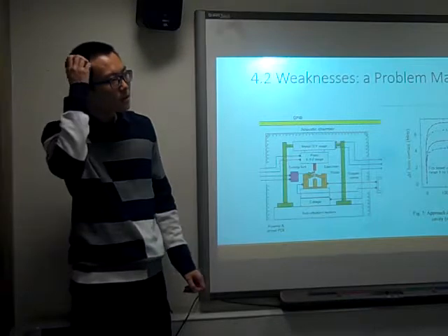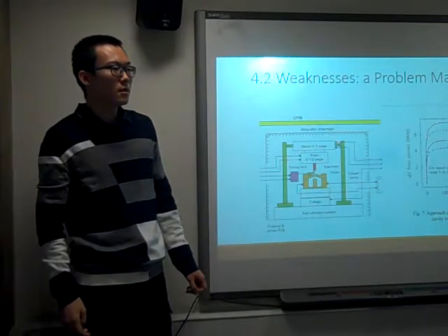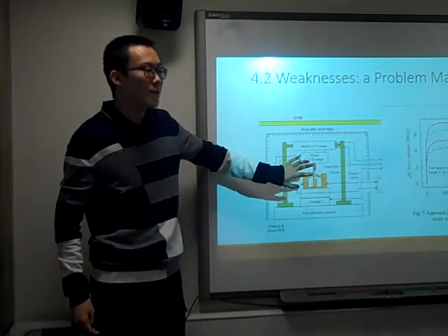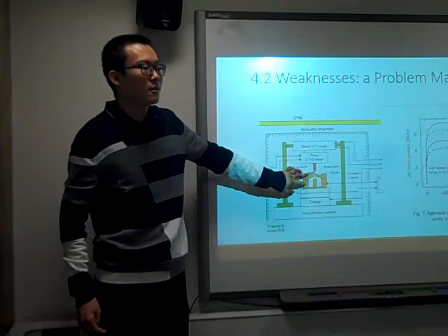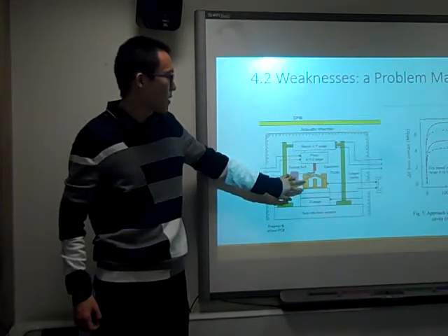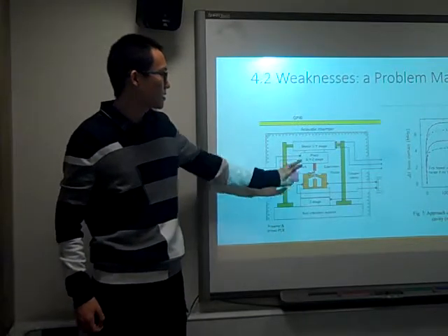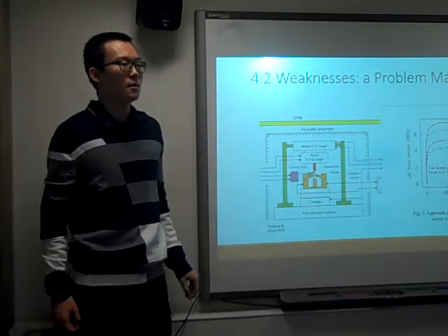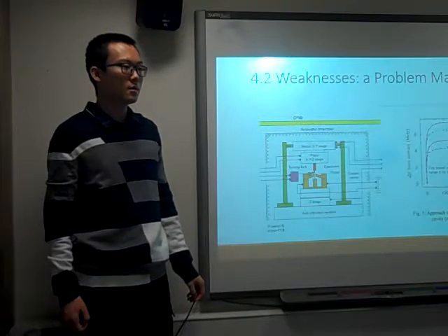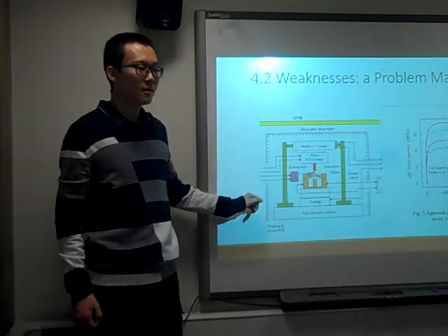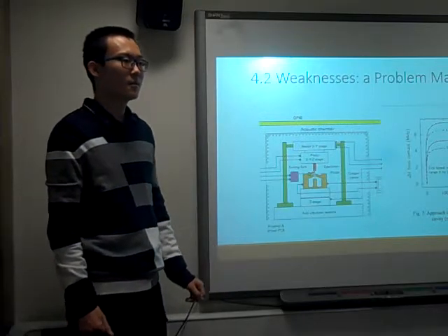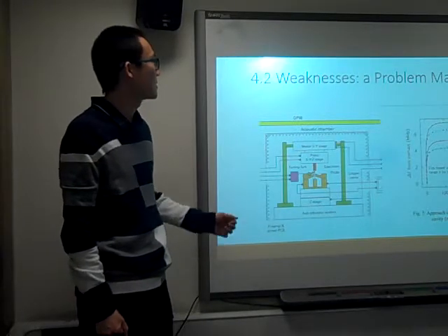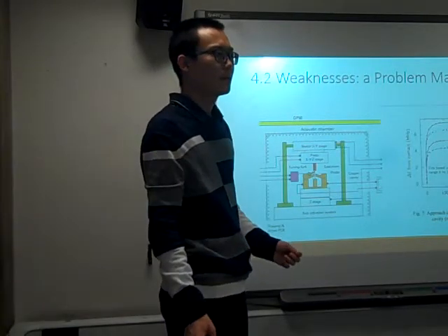But the holder also has some cables. If you move the sample, yeah, but if we move the sample, it will do nothing to the NSMM. Really? So most of the cables link the NSMM and the analyzer, but the specimen or the sample is separated from the system. So why do we have to move the Z stage? We just do scanning. Okay. So when you're scanning, it will move. Yeah, we have to move because of the scanning, to narrow the gap.